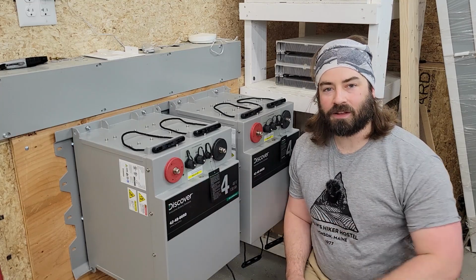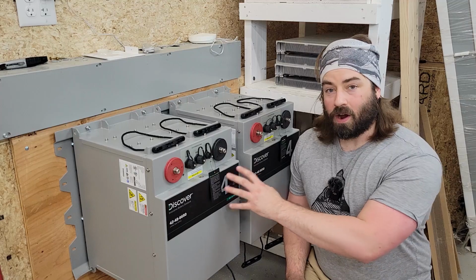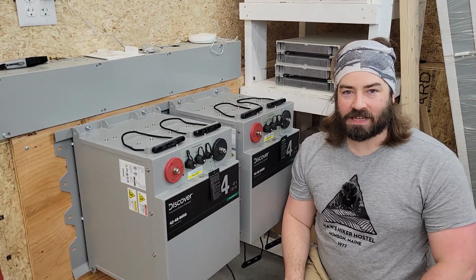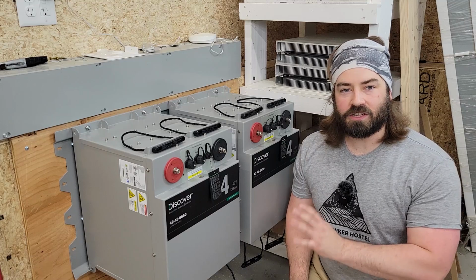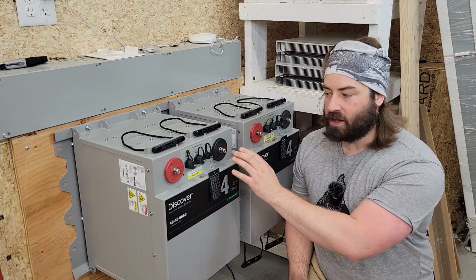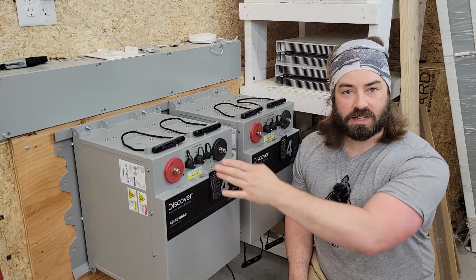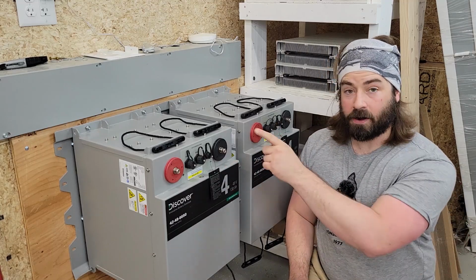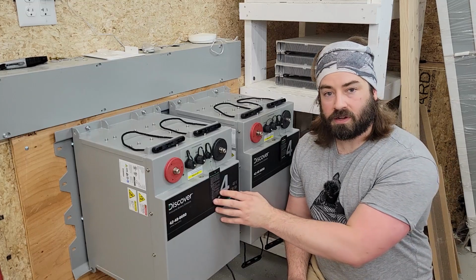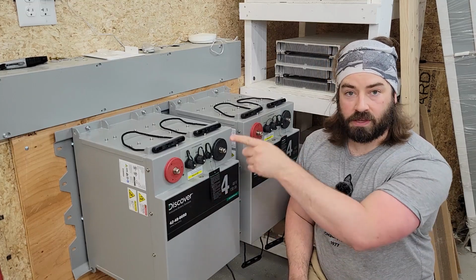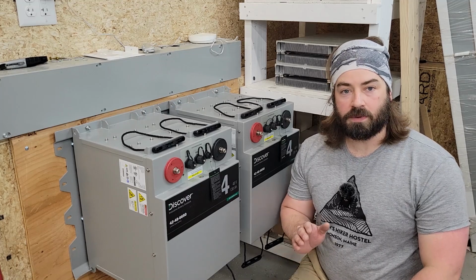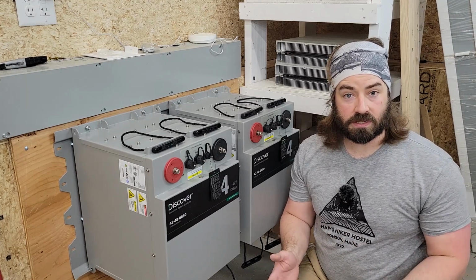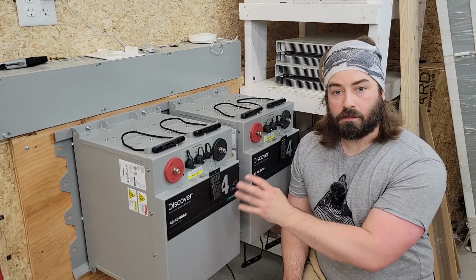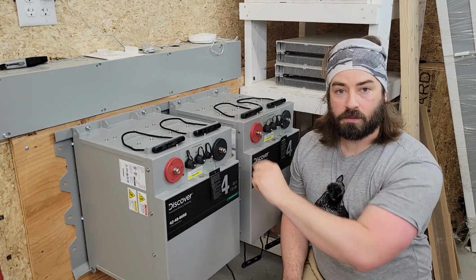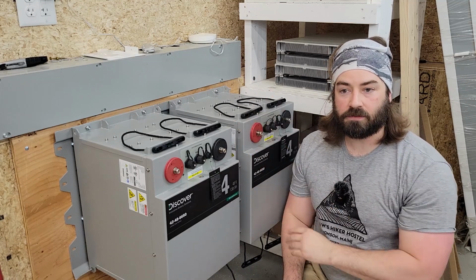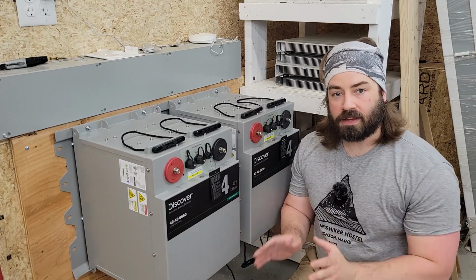With the batteries securely mounted to the wall, the next step is to wire these up to the inverter. As I've mentioned in past videos, I love bus bars. The ideal situation is to run a dedicated wire from each terminal on each battery to a central bus bar. In this case, I have a pair of bus bars up on the wall, so if I ran an individual set of wires for each battery to the central bus bars, I'd want all the wires to be equal length, because we're trying to achieve equal resistance, and I'd go for 2-aught minimum.